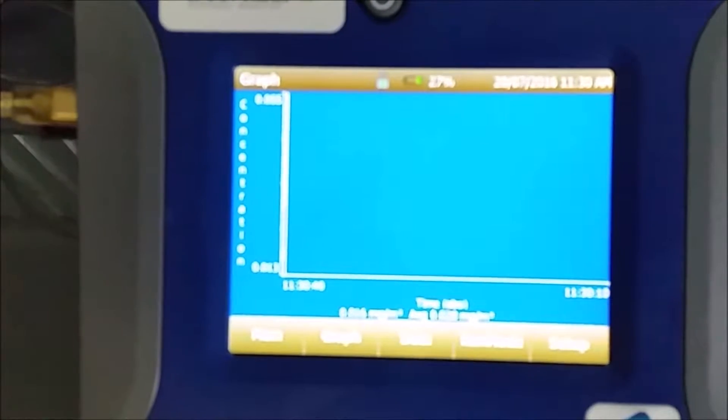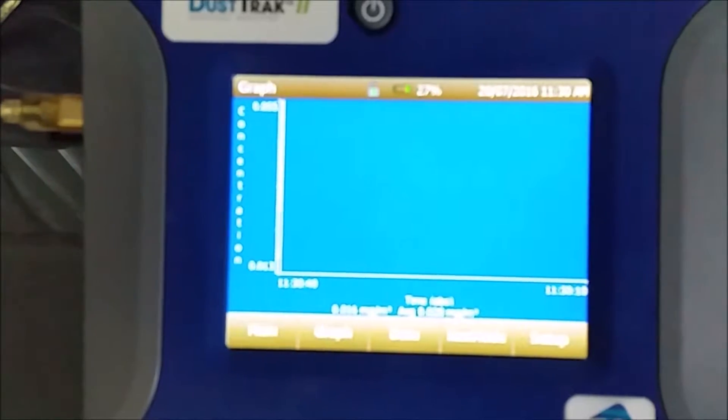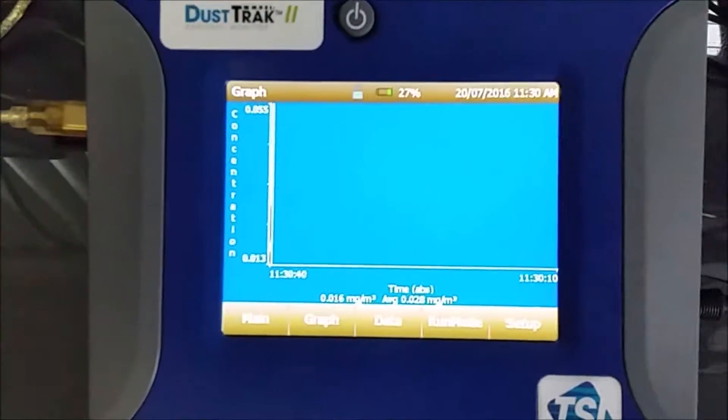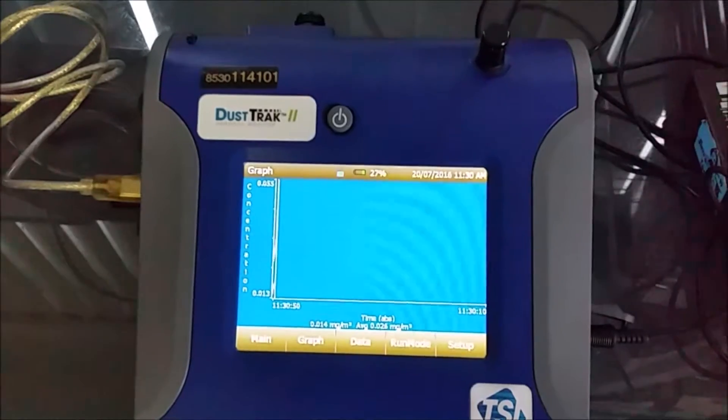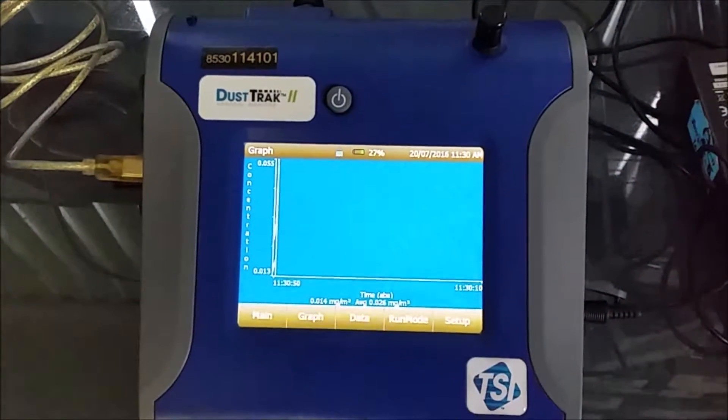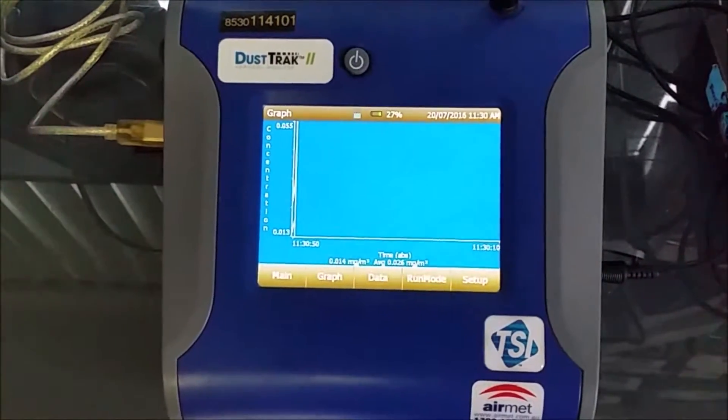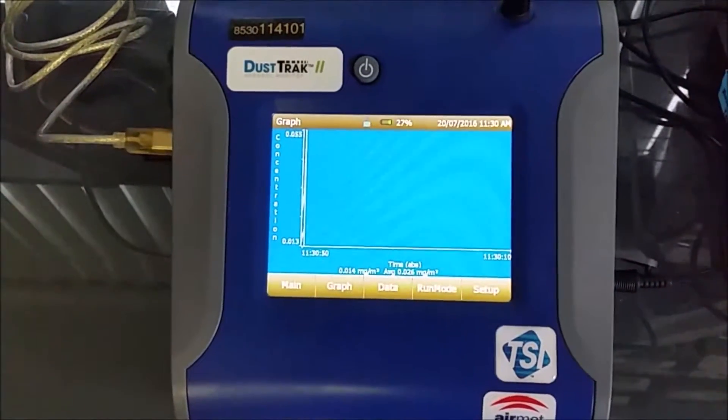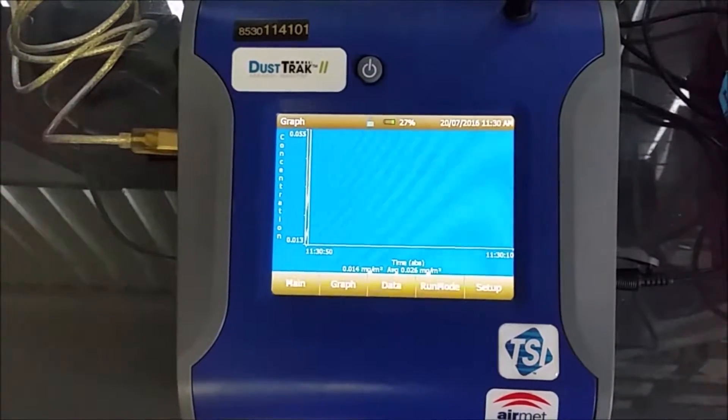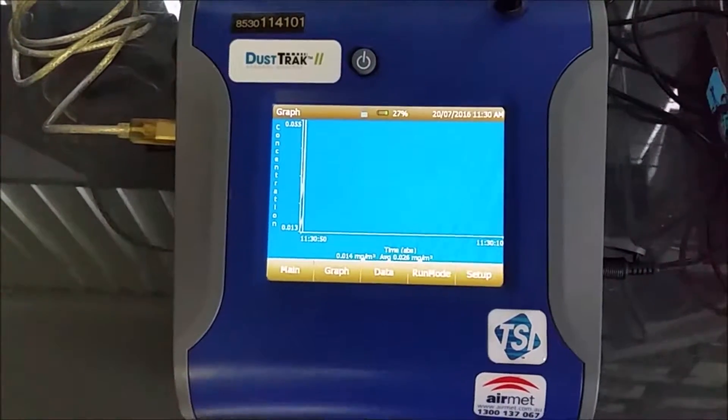With PM10, which is 10 micrometres in diameter, the dust particle, the actual guideline, indoor air quality guideline, is 0.05 milligrams per meter cubed.